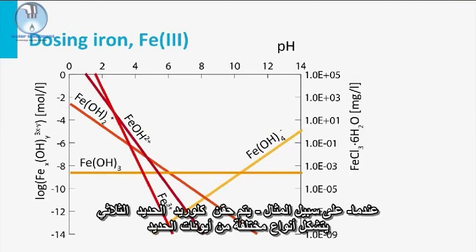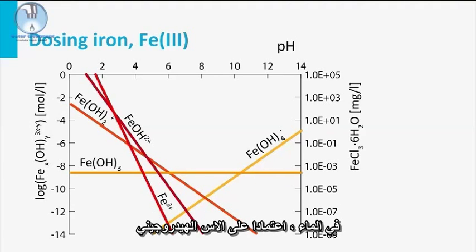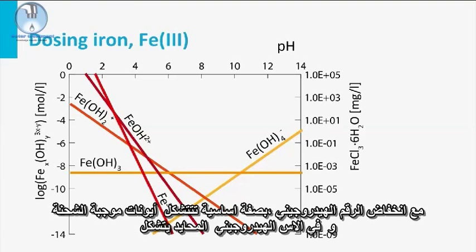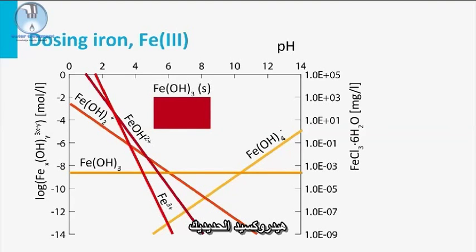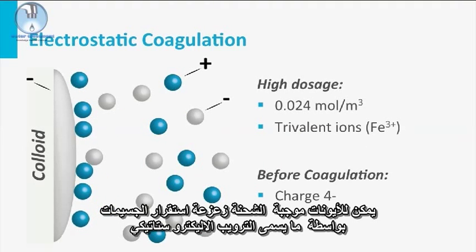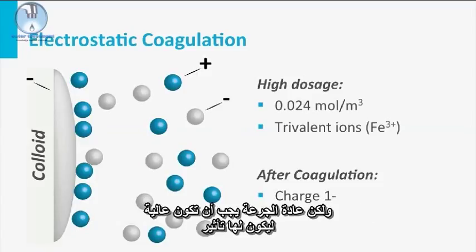When, for example, iron(III) chloride is dosed, different species of iron ions are formed in the water depending on the pH. With low pH, mainly positively charged ions are formed, and at neutral pH, mainly ferric hydroxide is formed. The positive ions can destabilize the particles by so-called electrostatic coagulation, but normally the dosage must be high to have an effect.